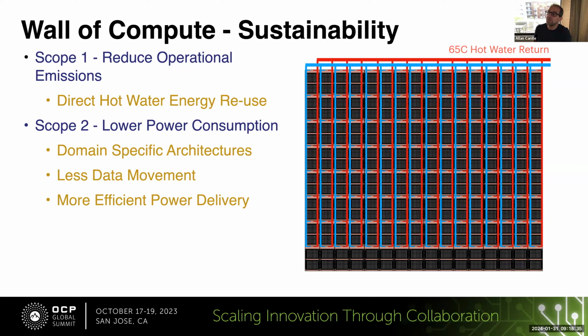In scope 2, since you're building a domain-specific architecture, if I need a Grace Hopper fat pipe, I can do that directly. I don't have to go up and down the switch network and burn a ton of power. We've got less data movement—these modules are inches apart. We don't have to go in and out through 18 inches to exit a 19-inch rack and back into a 19-inch rack. In two 1U boxes, the chips are only an inch apart, but we have to go through three feet of signal integrity loss and picojoules per bit to connect them, when in reality they're only a couple inches apart. So our 19-inch rack is now a module, a 3D module.